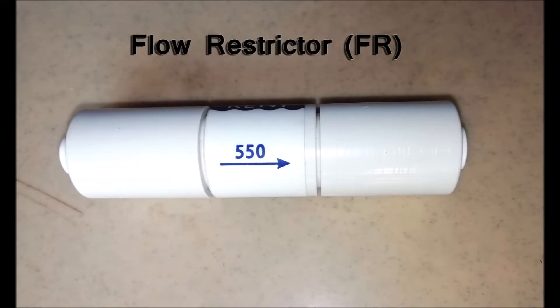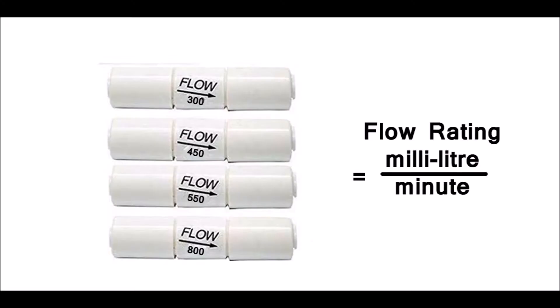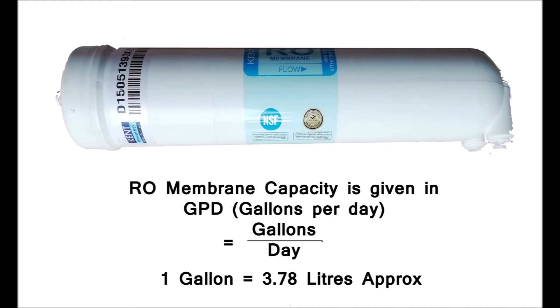Flow restrictors are available in various flow ratings and should be selected according to the capacity of the RO membrane. Let's see how we can find the matching flow restrictor for the RO membrane. The rating you see on the flow restrictor — such as FR300, FR450, FR550, FR800 — indicates the flow rating in milliliter per minute. The RO membrane capacity is given in GPD, gallons per day.